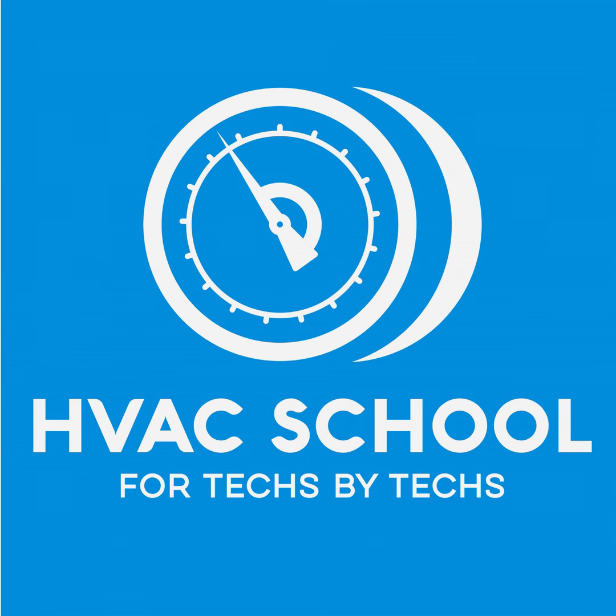So each one of these conditions will give you a multiplier. Outdoor air is going to give you this multiplier. Indoor air, it's going to give you this multiplier. Piping total equivalent length, it's going to give you this multiplier. Those are three of the major factors, in my opinion, that go into how much actual capacity you get of your outdoor unit. So you also need to know what your block heating and cooling loads are.